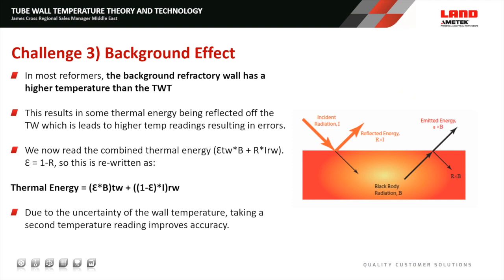The third challenge is background effects. The background refractory in a reformer is often higher in temperature than the tube wall. The tubes are being heated by radiation from the refractory, so what our pyrometer sees is the incident radiation from the refractory combined with the radiation emitted from the tube. We need to ensure our final reading corrects for this additional thermal energy from the background using the correction equation shown. We always need to take background temperature measurements to avoid reading too high. The incident radiation effect will be higher with a more reflective surface, which is why we need to correct for both emissivity and background effect.